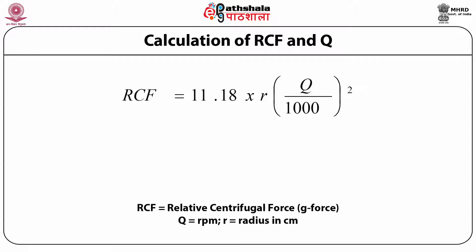Stokes' law clearly verifies the mathematical expression of molecule behavior during centrifugation and what factors affect separation. There is also a conversion between RCF and RPM: RCF = 11.18 × R × (RPM/1000)². To convert RCF to RPM, the equation is: RPM = 299 × √(RCF / R). These two equations are used for interconversion between RCF and RPM.